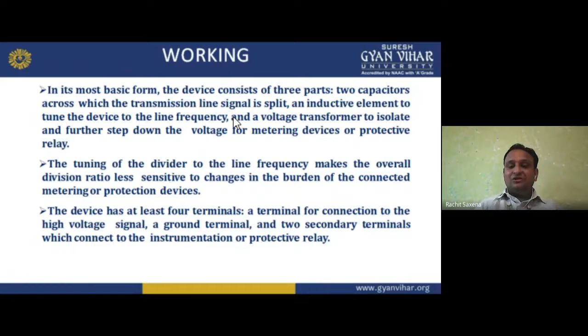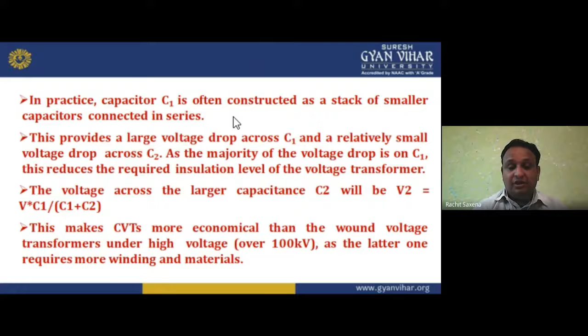In practice, capacitor C1 is often considered as a stack of smaller capacitors connected in series. This provides a large voltage drop across C1 and a relatively small voltage drop across C2. As the majority of the voltage drop is on C1, this reduces the required insulation level of the voltage transformer. Now the voltage across the large capacitance C2 will be V2 = V × C1/(C1 + C2). This makes CVTs more economical than the wound voltage transformer at high voltage, over 100 kilovolt, meaning 100 × 10^3, that is 1 lakh volt we can say. The latter device requires more winding and materials, so for voltages above 100 kilovolt the CVT is more economical than the wound voltage transformer.